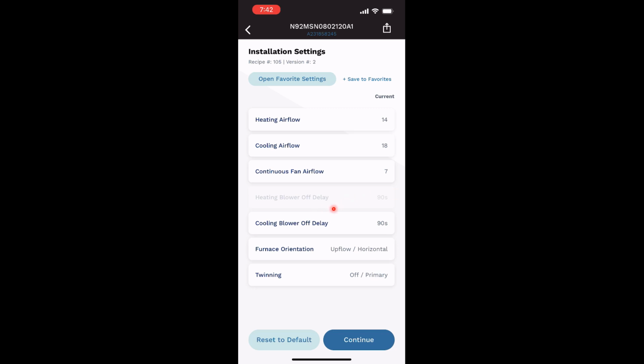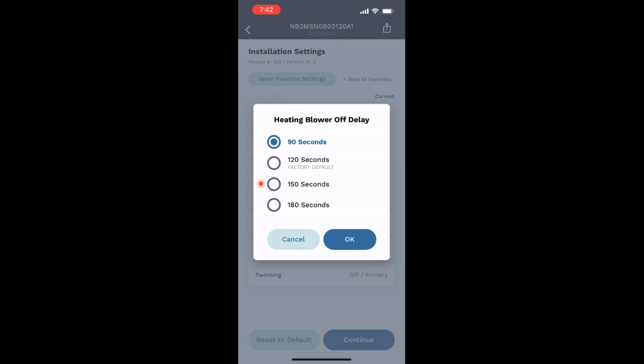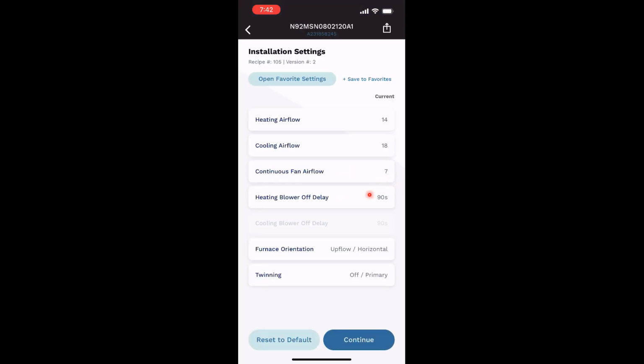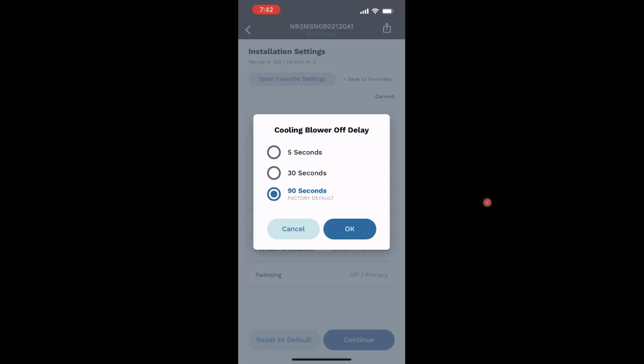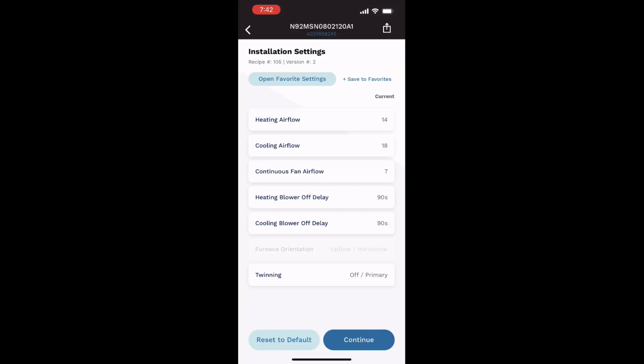All right, then we look at our heating blower off delay. We're going to select it, and this is the screen that pops up. So you have an option to go 90 seconds, 120 seconds, which is your factory default, 150 to 180. You click OK. You go back to cooling off delay, and you can go 5 seconds, 30 seconds, or the factory sets at 90 seconds, and you click OK, and you go back to this screen.